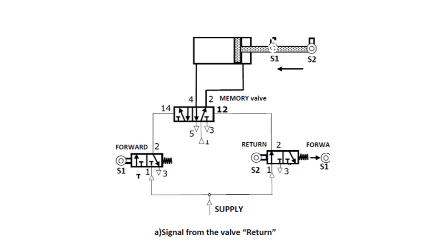So this was the same example that I took initially. Here they used a normal roller operated direction control valve to get the oscillation movement. Right? If you use one idler roller, it won't retract back automatically. Then you need to generate the signal yourself, or you need to eliminate the S1 switch. You need to use only one switch. When you reach the end point, you have to generate the signal, if you use a single acting cylinder.